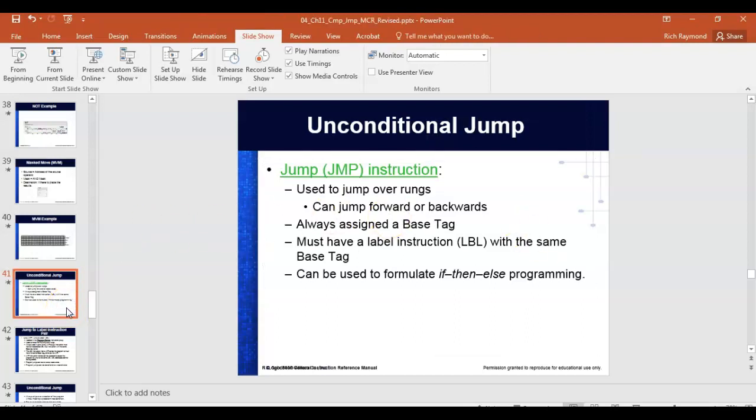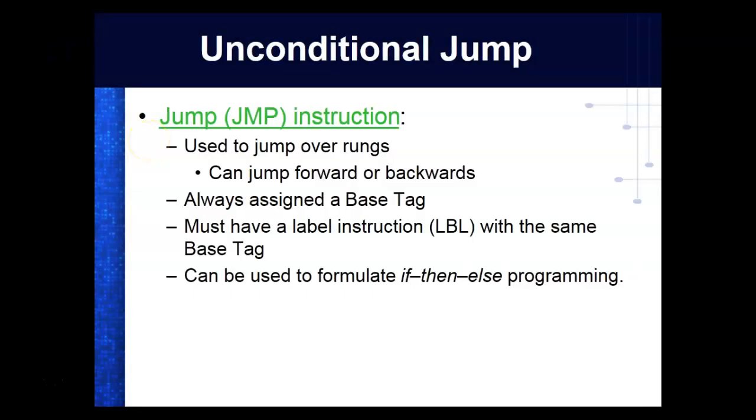In RSLogix 500, we use a U for U1, U2, and stuff like that. Here we're going to use a tag, so this is a lot easier to understand. Always assign a base tag. Must have a label instruction with the same base tag. Can be used to formulate if-then-else programming.